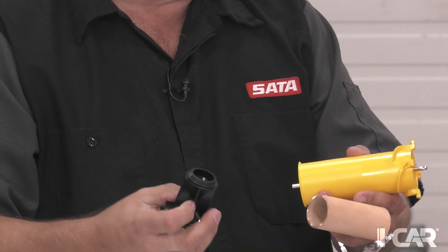You can wash the plastic components in soapy water and dry them. The sintered bronze element, use a clean thinner or acetone to clean it with a soft scrub brush, and blow it completely dry. Once it's dry, it just drops back into the canister and reattaches.